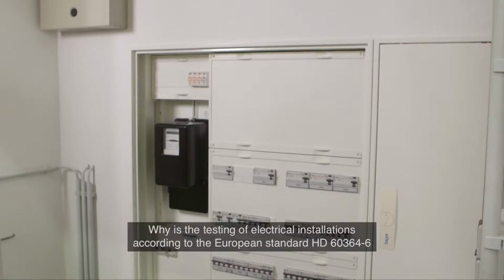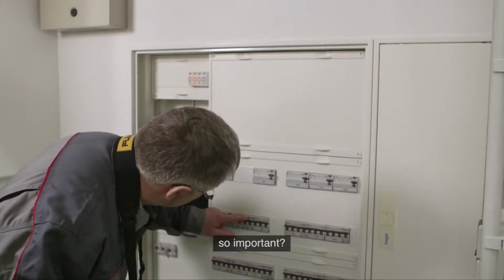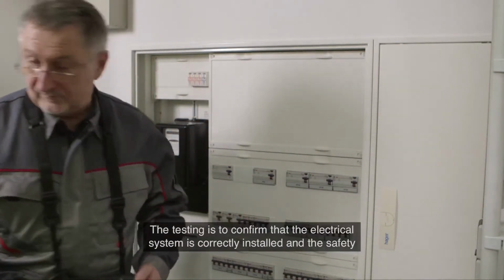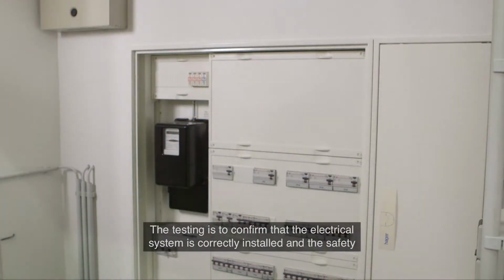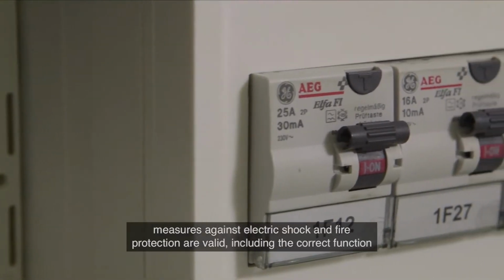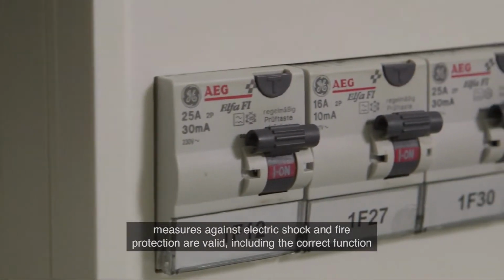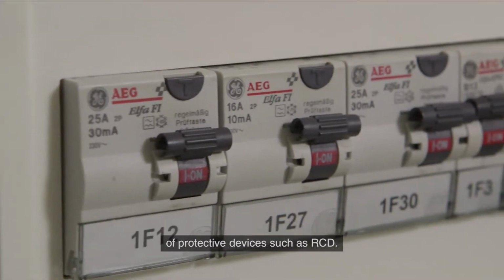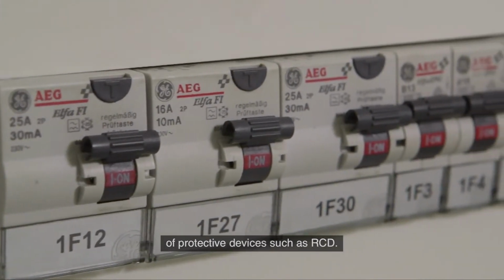Why is the testing of electrical installations according to the European Standard HD 60364 Part 6 so important? The testing is to confirm that the electrical system is correctly installed and the safety measures against electric shock and fire protection are valid, including the correct function of protective devices such as RCD.